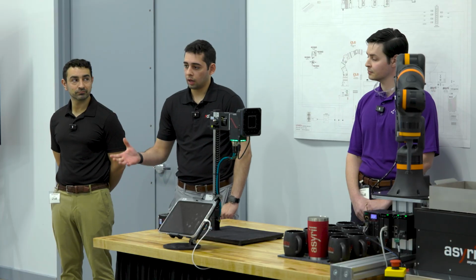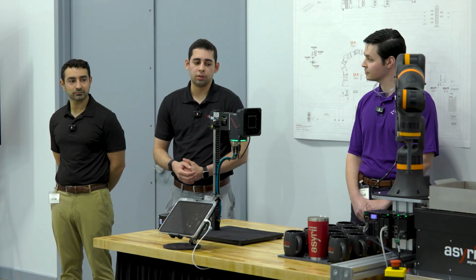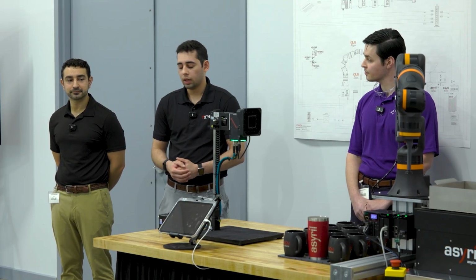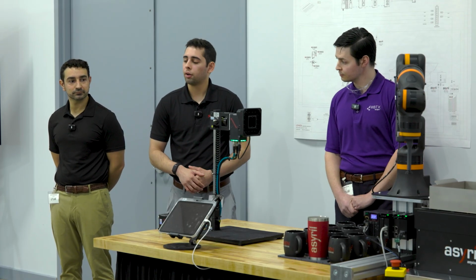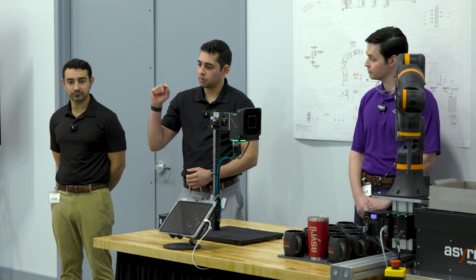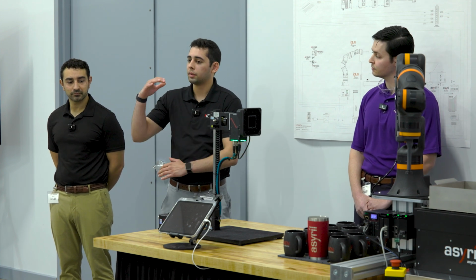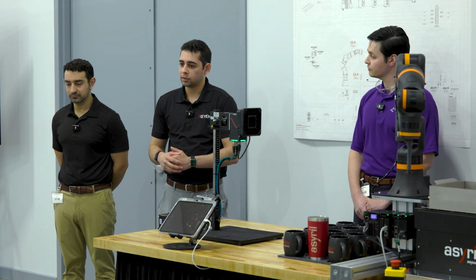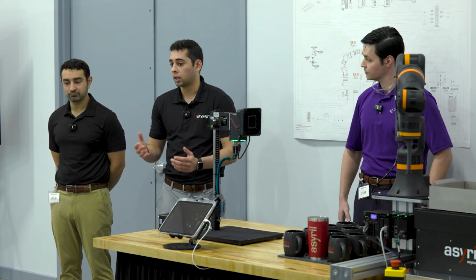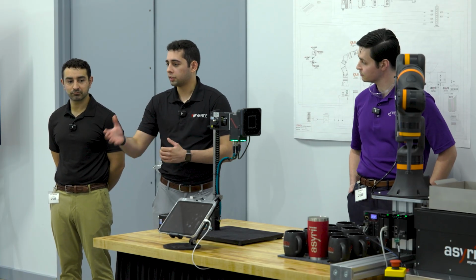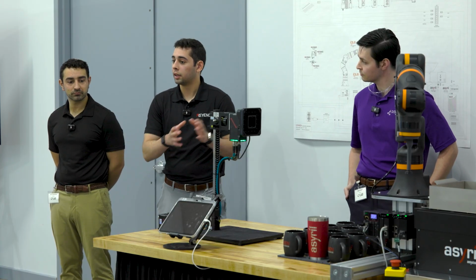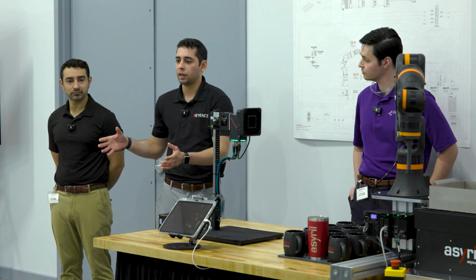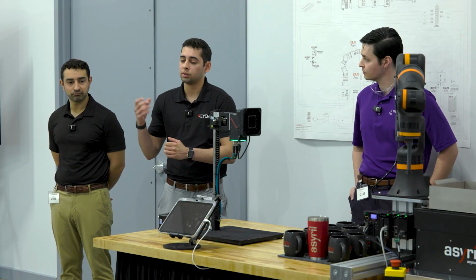So both. Typically how we'd set this up, if you were to troubleshoot an Allen Bradley PLC, we have a custom feature called PLC Link. You select the PLC that you'd like to connect to; there's a whole drop-down of models. Type in the IP address, we hit a read tag button, and you have 1,000 tags in less than a couple seconds. From there, I would ask, what relevant tags are related to the issue that you're seeing? Are there alarms that we can use as triggers? Or you can go into Studio 5000 and create a different bit that is now used as your trigger.